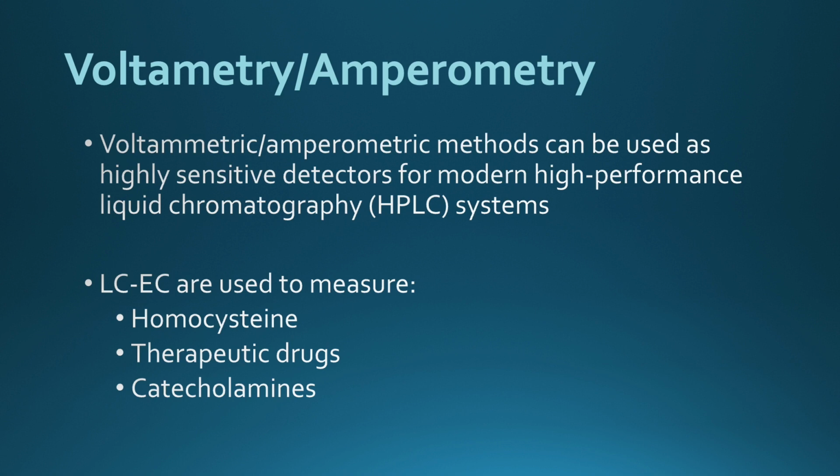electrochemistry. Disadvantages? Maybe, as we said, it is affected by hyperlipidemia. Temperature. Fragile, it breaks, I must keep it in a certain place. There is a very common disadvantage which is protein coating, contamination. There may be interferences, but with the current electrodes these interferences are minimized. But there is a problem, which is protein coating. Protein in the samples can deposit on the electrode and prevent the reaction.